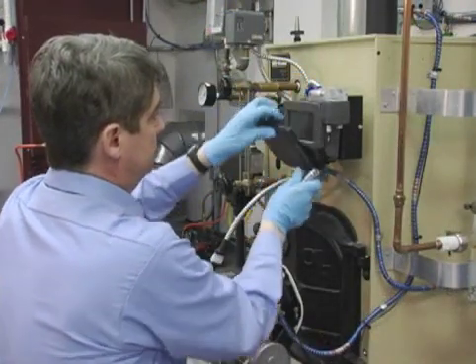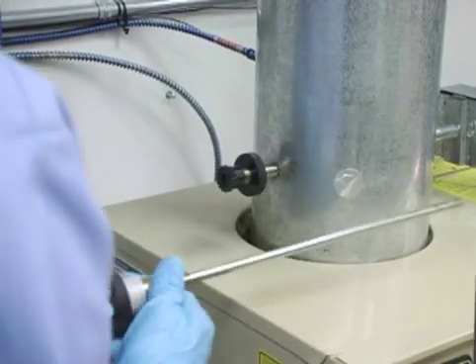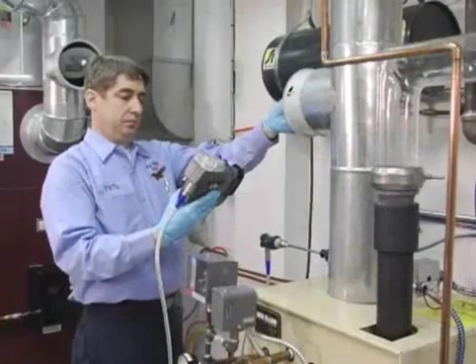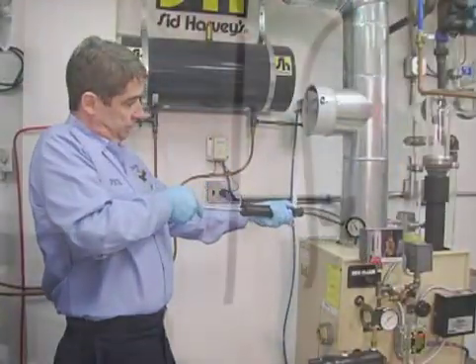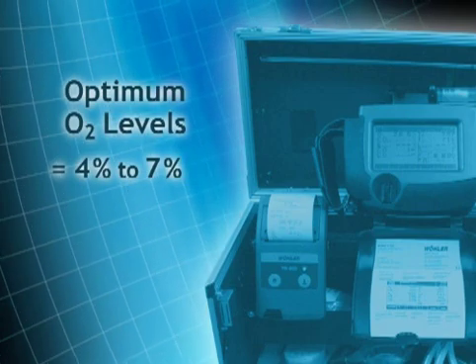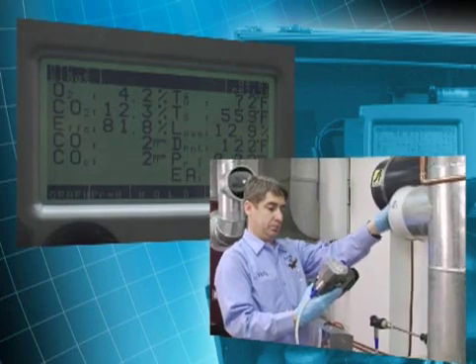Connect the flue gas sampling probe assembly to the analyzer per manufacturer's instructions. Start the analyzer and allow it to complete the self-check process. Insert the probe into the center of the flue to check for sufficient draft at the breech, and then verify you have the manufacturer's recommended draft over the fire. If necessary, adjust the draft regulator until the readings are acceptable. If you adjusted the draft regulator, repeat the smoke test procedure to assure that the unit is still operating at zero smoke.